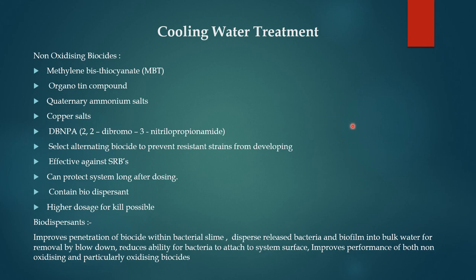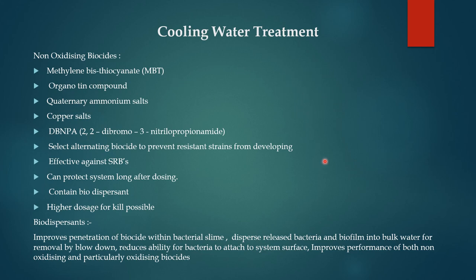During non-oxidizing biocide dosing, oxidizing biocides are not used. In closed-circuit cooling water (CCW) systems, only non-oxidizing biocides and biodispersants are used to control microbiological growth. This covers scale control, corrosion inhibition, corrosion control, and fouling control including microbiological growth and its treatment method using chemicals.